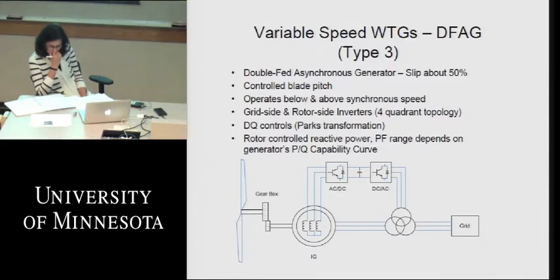You'll see in the diagram there the AC-DC converters, and between the generator itself and the grid we're showing a three-winding transformer. So we tap a little bit of the output power from the stator and feed that back to the rotor circuit, and then we control that current we're tapping back to the rotor through the power electronics to control, again, the current magnitude and phase.